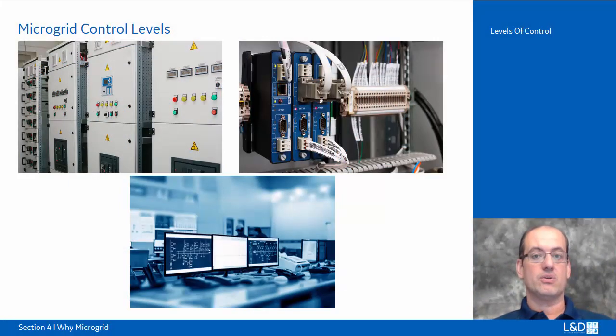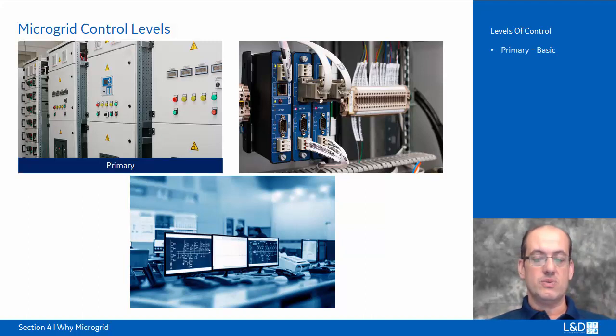Now we have a microgrid, and the question is what level of controls are we having in the microgrid? What type of controls? We start with the primary level. A primary controlled grid is a simple generation point that feeds power, and the power is fed with the minimum requirements that meet the standard of the local utility. So it just provides enough power. It kicks in when the utility cannot provide the power to the local entity, and it has no automated control available.